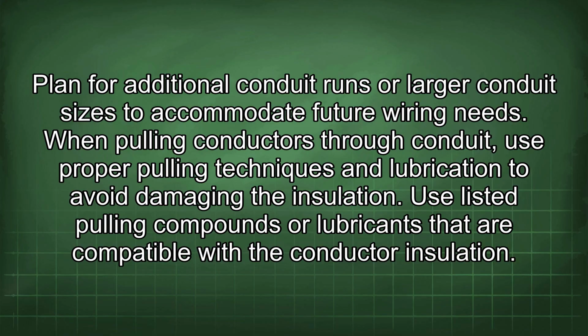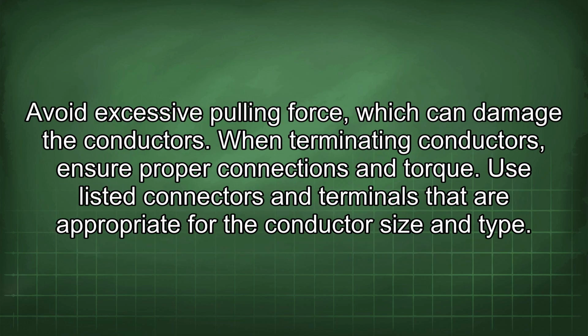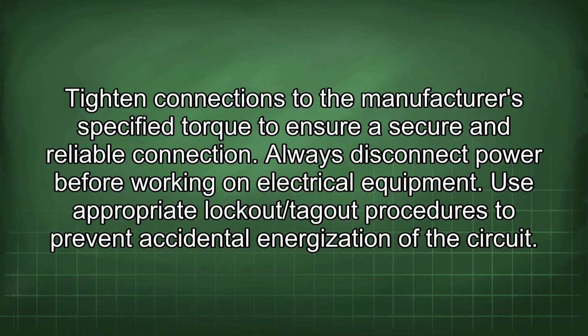When pulling conductors through conduit, use proper pulling techniques and lubrication to avoid damaging the insulation. Use listed pulling compounds or lubricants that are compatible with the conductor insulation. Avoid excessive pulling force, which can damage the conductors. When terminating conductors, ensure proper connections and torque. Use listed connectors and terminals that are appropriate for the conductor size and type. Tighten connections to the manufacturer's specified torque to ensure secure and reliable connection.